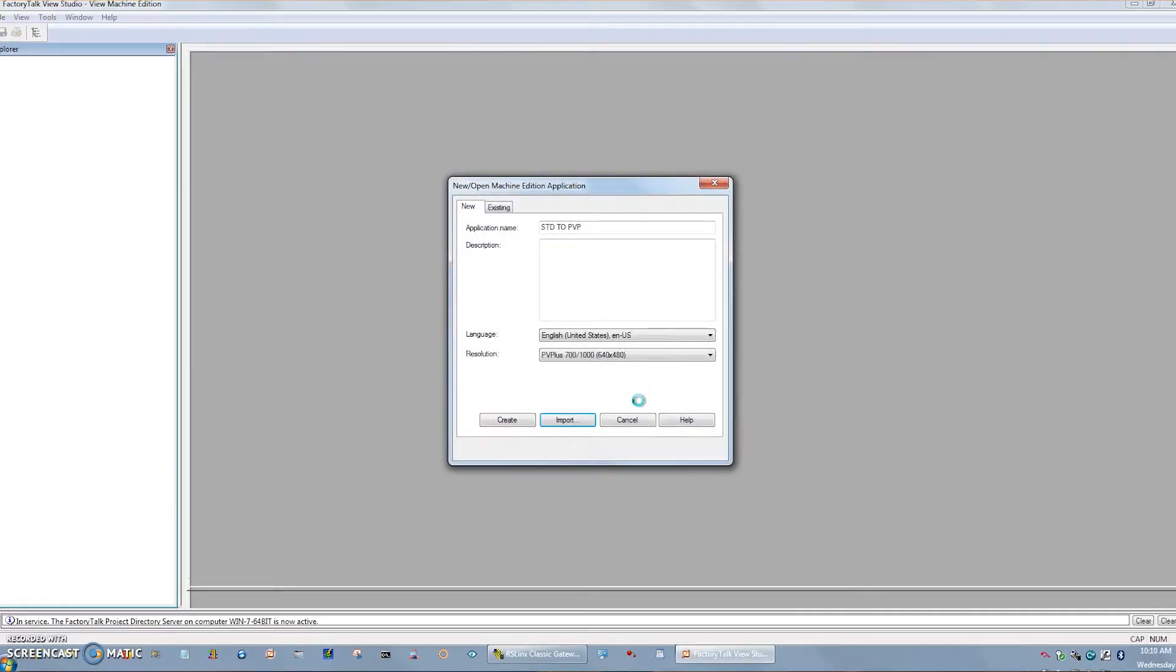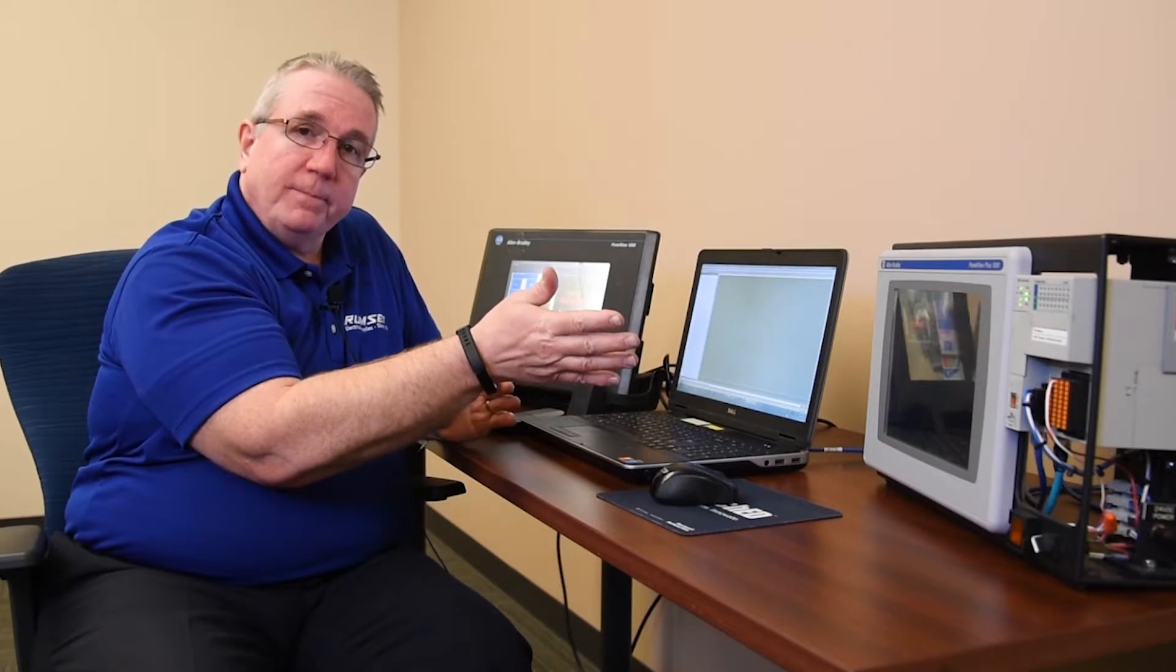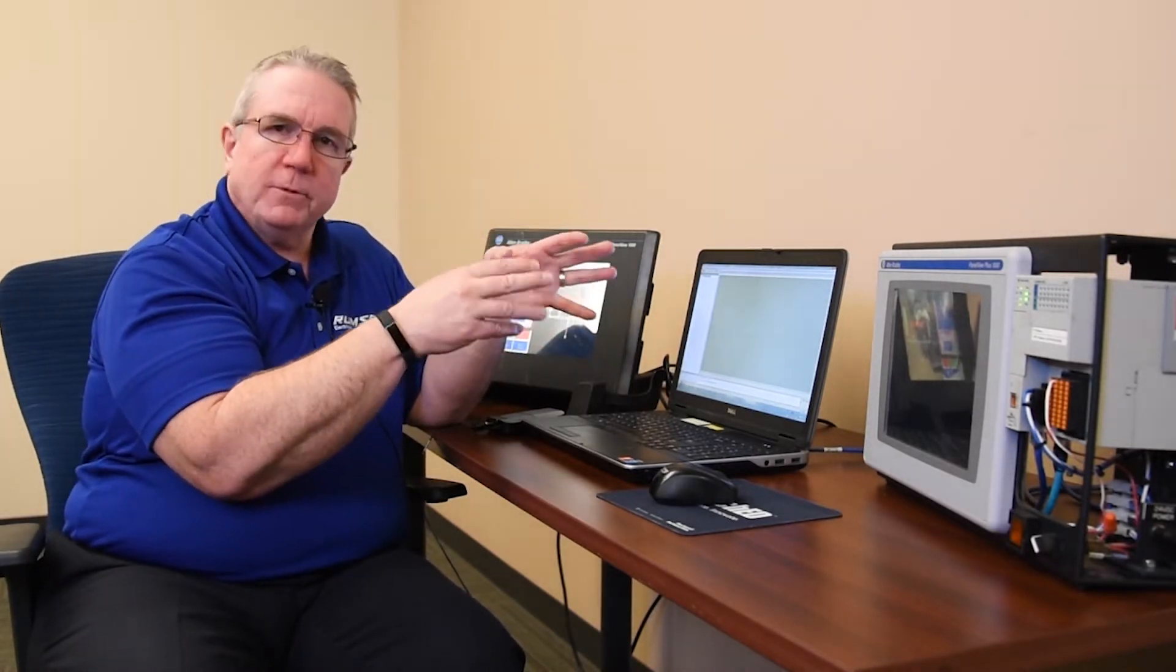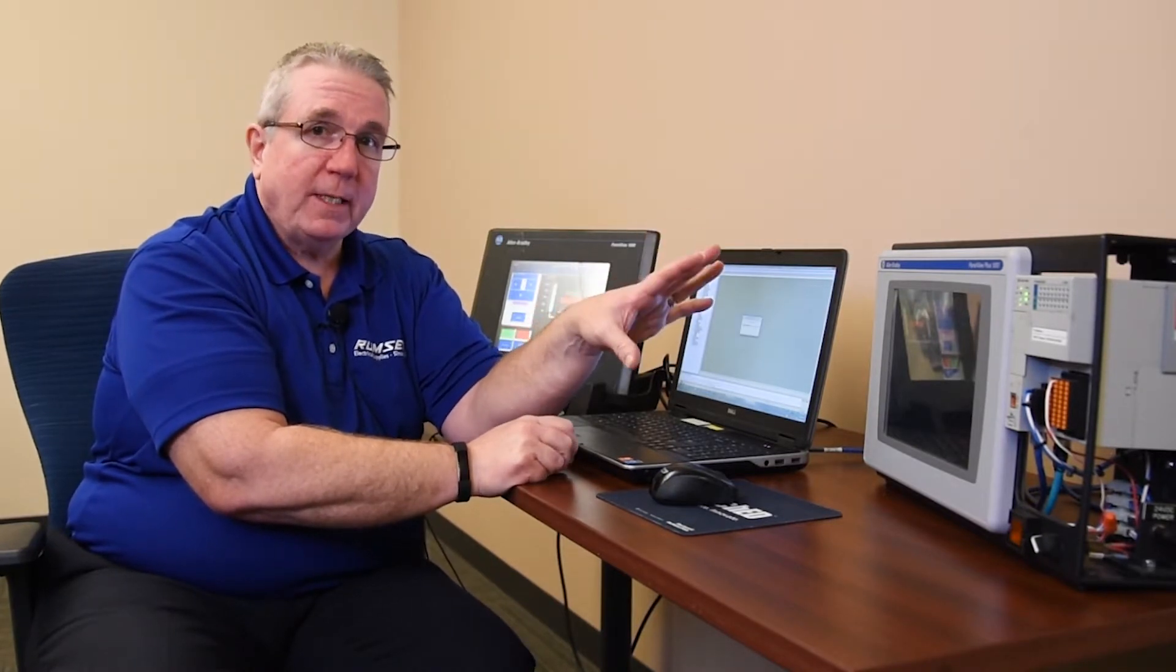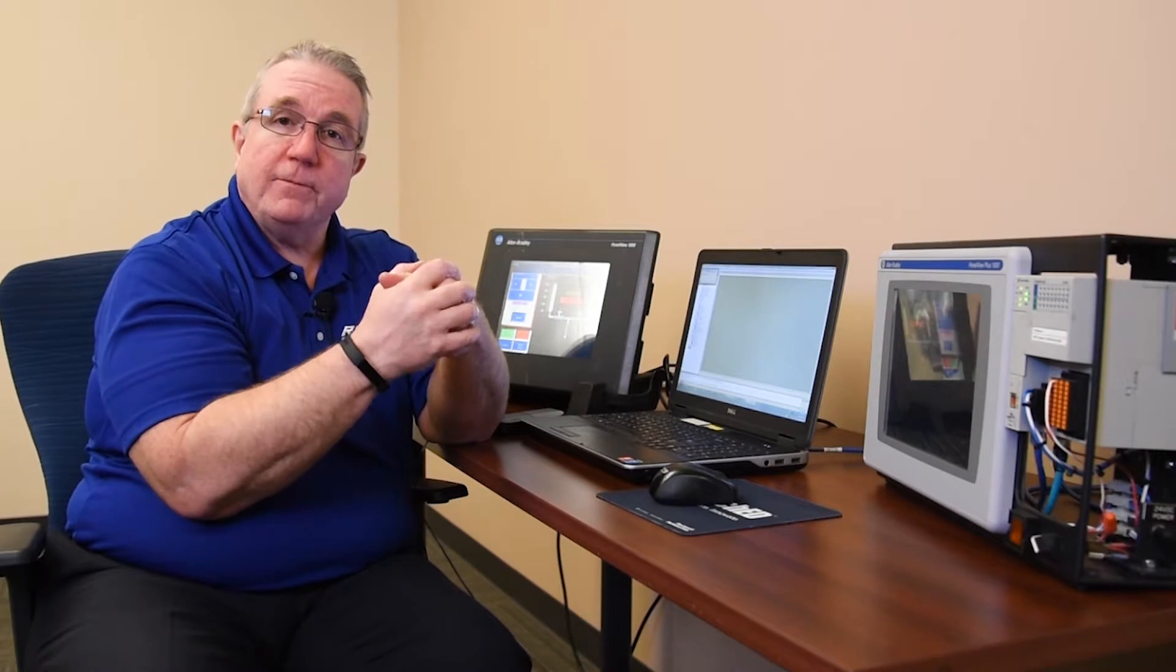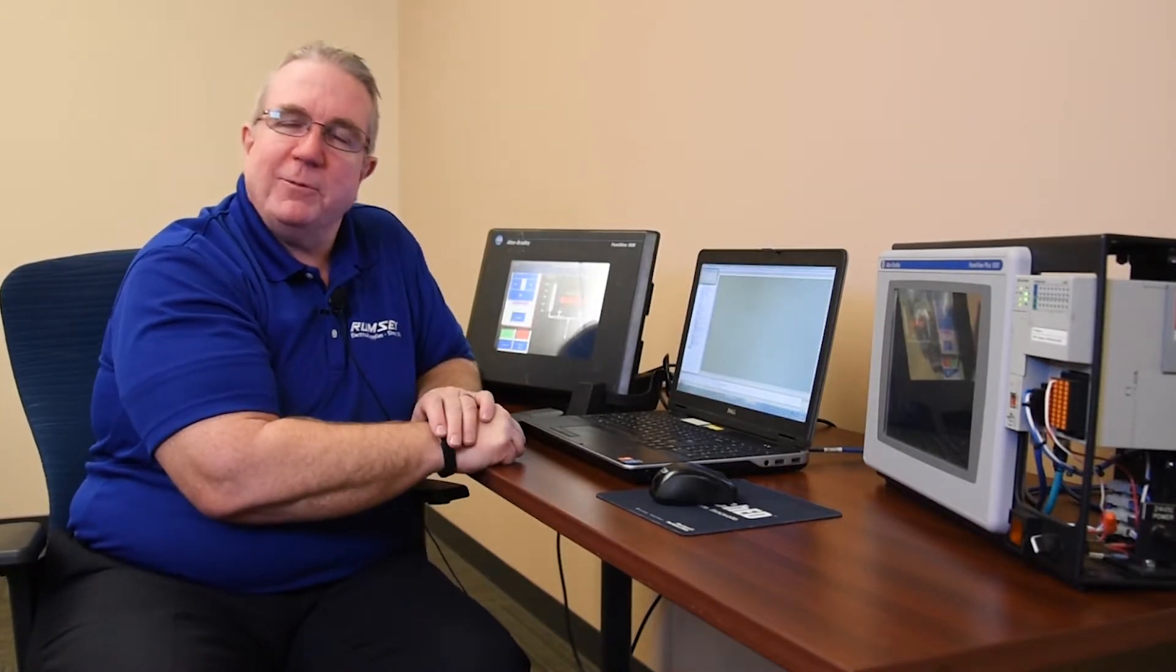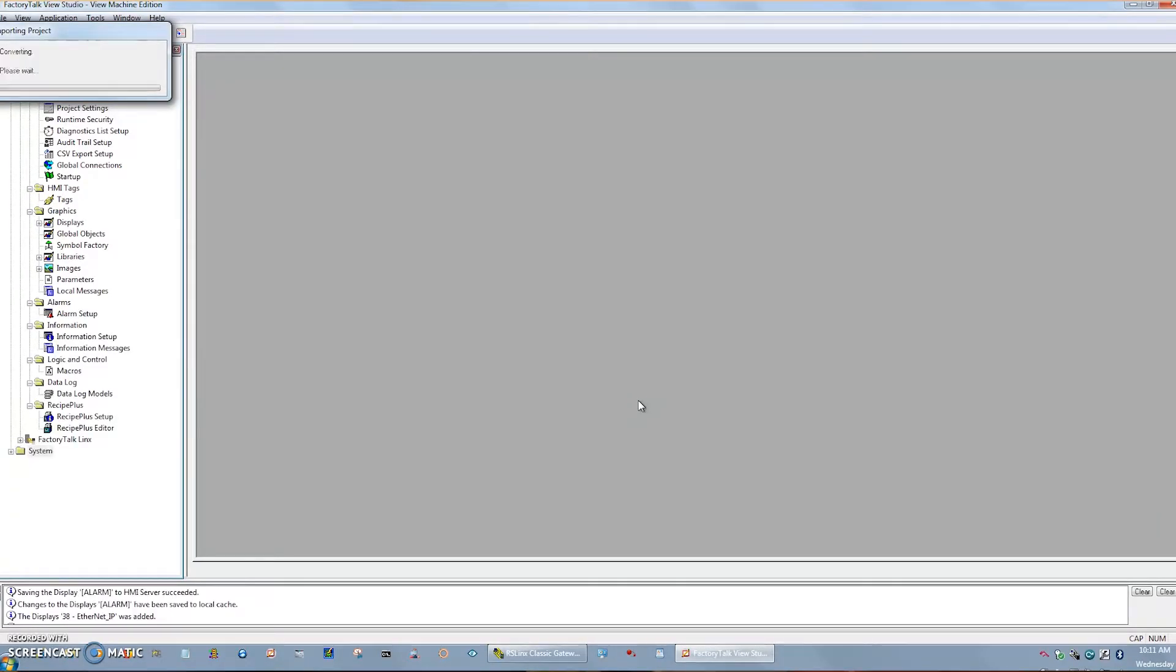And you'll find this usually takes about a minute. It really depends how many screens you have. One thing to always keep in mind, the machine edition for PanelView Pluses does not have a screen limit. So you do not have to worry about it being only 25 screens or 30 screens or whatever. If it's a PanelView Plus compact, which is not a PanelView Plus standard or regular performance in nowadays terms, then you might get into a screen count issue. So again, have a little knowledge of the first project you're going to convert. And if it gets around that 15, 25 screen range, give us a call. We can help you make sure you have the new products chosen correctly. So now you can see it's just cranking through the graphics and converting everything.